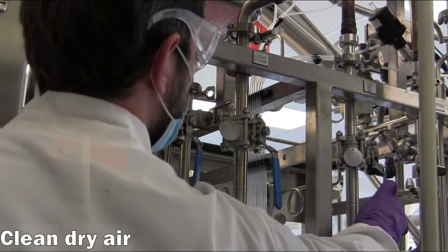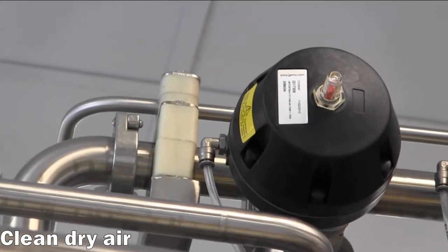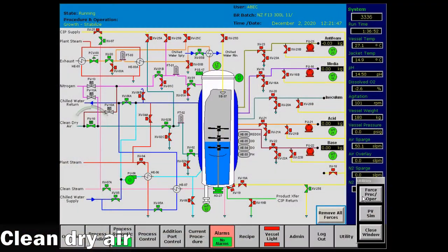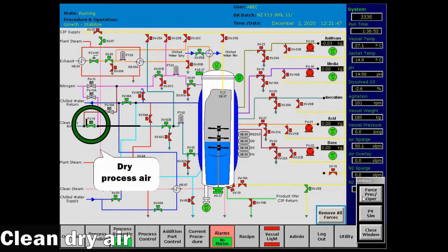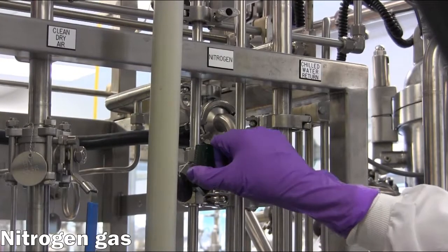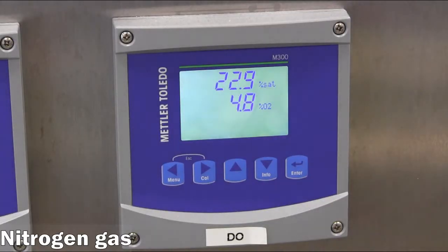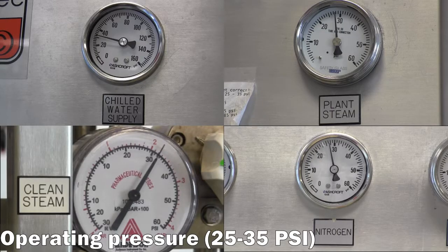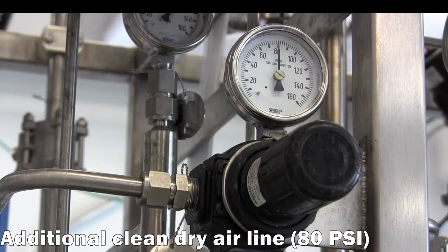Clean dry air is used for pneumatic valve operation and is process air which is supplied to the reactor during operation. And nitrogen is sparged to get a 0 point for the dissolved oxygen calibration. The operating pressure for all utilities should be regulated between 25 and 35 psi. One exception is clean dry air, for which the additional connection at 80 psi is required.